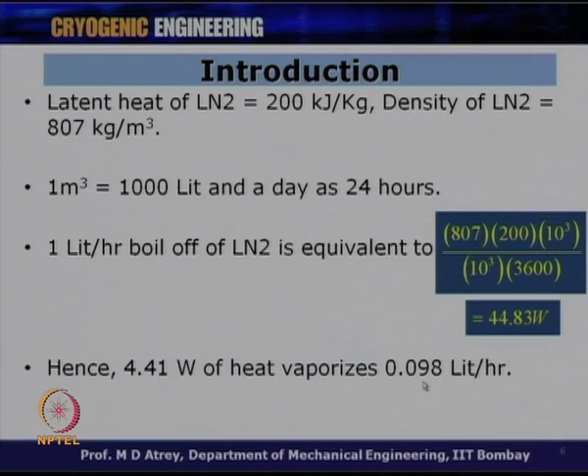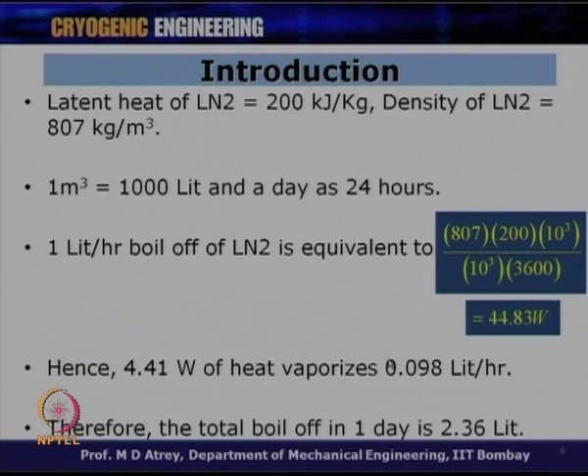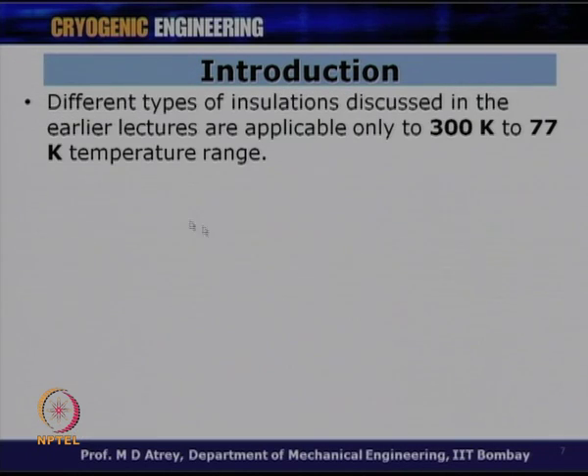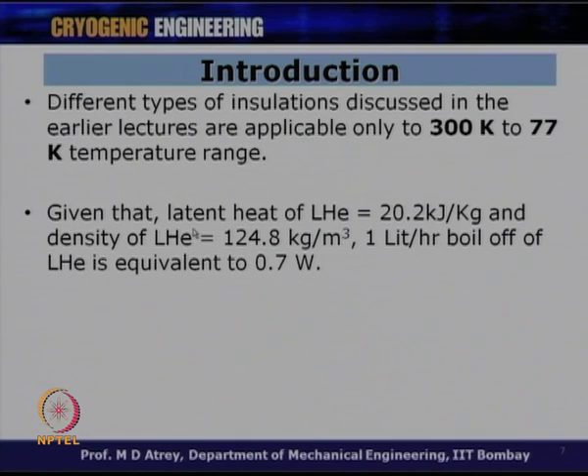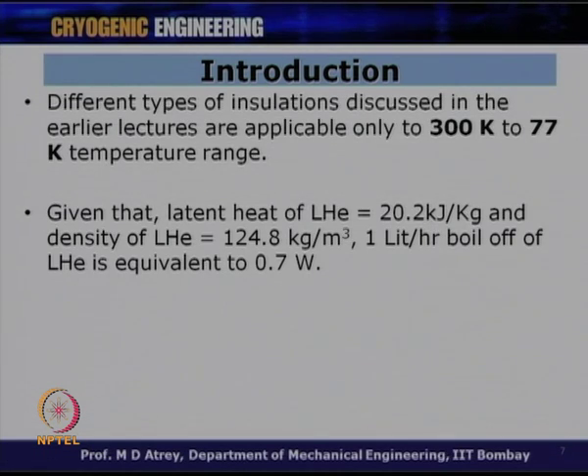The different insulation types discussed are applicable only to the 300 K to 77 K range. However, for liquid helium, the latent heat is only 20.2 kJ/kg — about 10 times less than liquid nitrogen — and its density is 124.8 kg/m³. Repeating the calculation for liquid helium, 1 liter per hour boil-off corresponds to only 0.7 W of heat in leak.